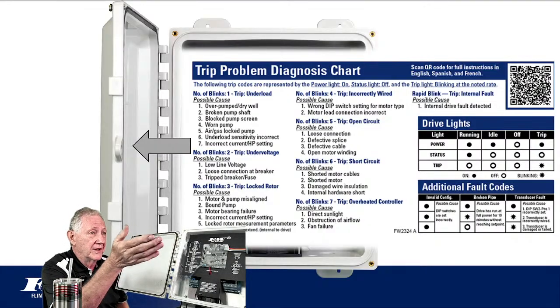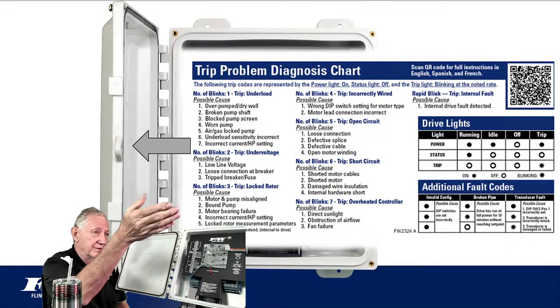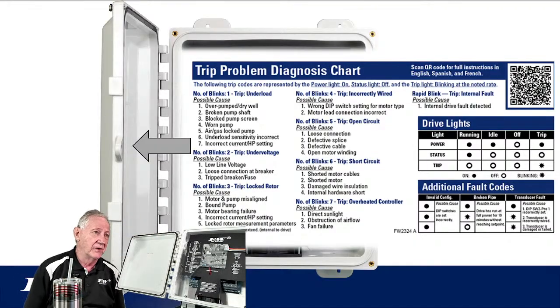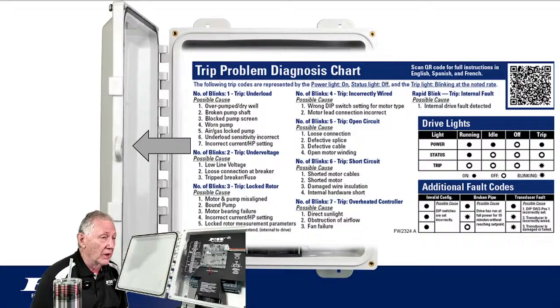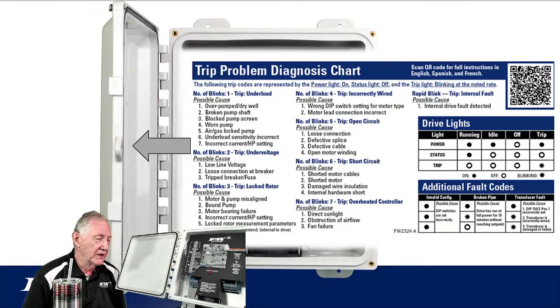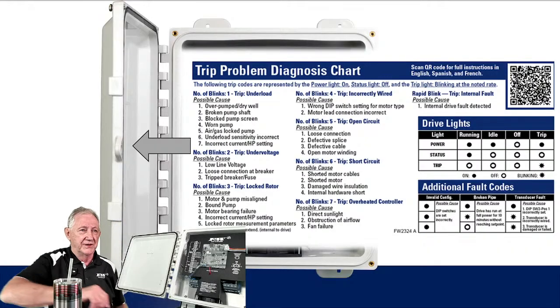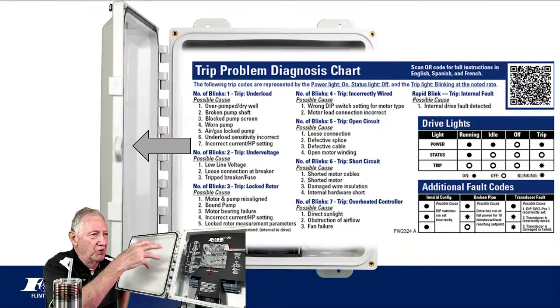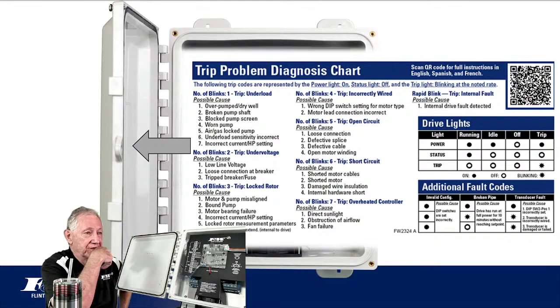So in other words, if you've got a blinking red light, there's a single blink, two blinks. The single blink is an under load, two blinks is under voltage, three blinks is a locked rotor. These are sequential blinks. Four blinks is an incorrectly wired drive, and so forth. In addition to the troubleshooting with the red light blinks, you've also got the power light and the status light. This label is going to tell you everything you really need to know about those lights up front. When you understand that, then you understand what the drive's telling us.